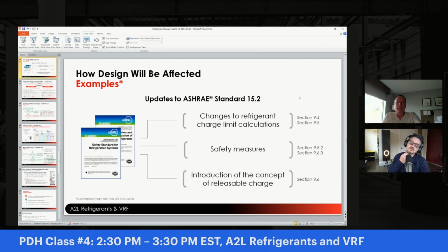Now moving to standard 15.2. Standard 15 is the commercial side and 15.2 is the residential side. So 15.2 and UL were updated with some new details and safety measures, just like standard 15, to support the safe use of these refrigerants. 15.2 is an application safety code, and again, the UL code is the equipment or product safety standard. They've included a lot of major changes here to the refrigerant charge limit calculations. They've added some safety measures and introduced that concept of releasable charge on that side as well.